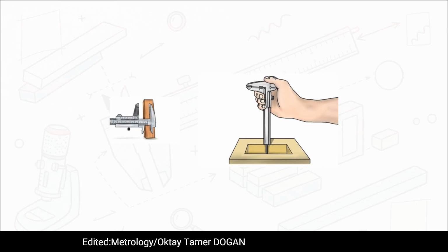Actually, here's a quick pro tip straight from the guidelines. It's best practice to use gauge blocks with fractional values, like 41.3 millimeters, instead of perfectly round numbers, like 50. Uneven testing helps verify the linearity of the scale across the whole beam, rather than just repeatedly checking the exact same digital increments over and over.